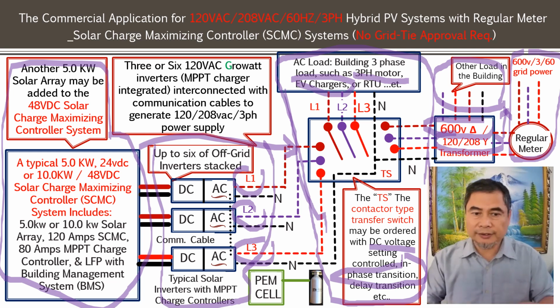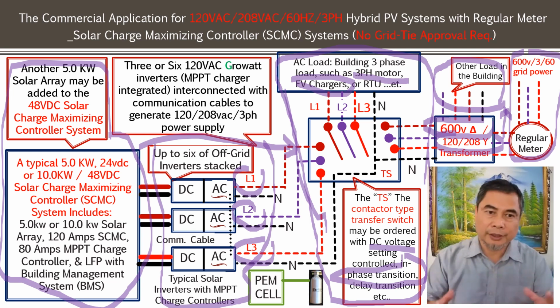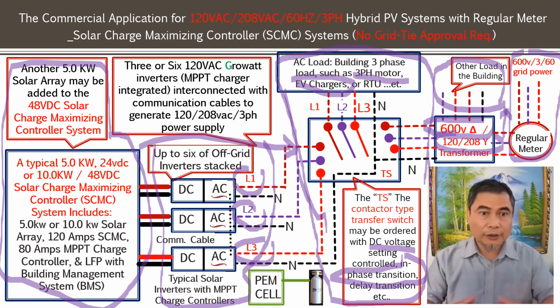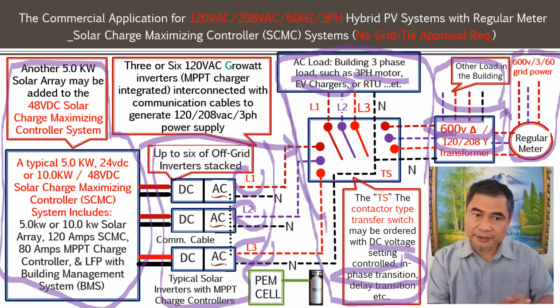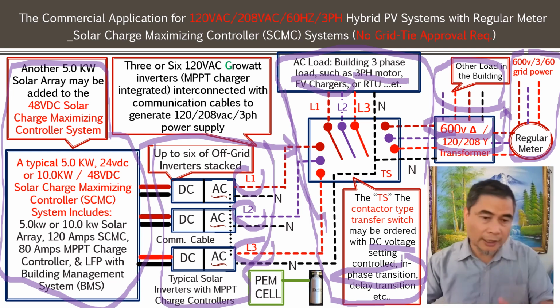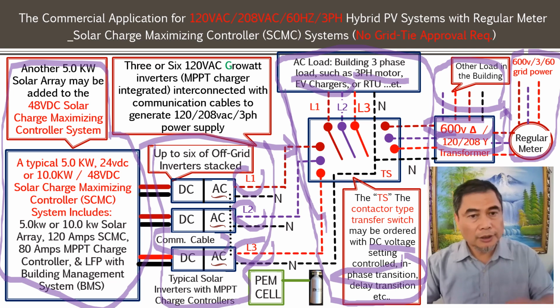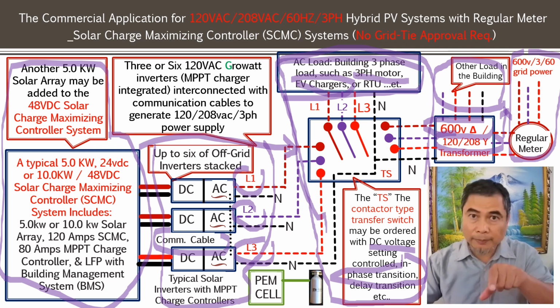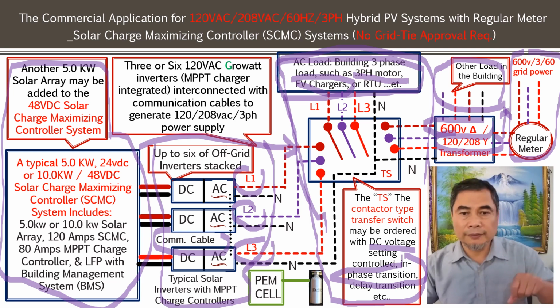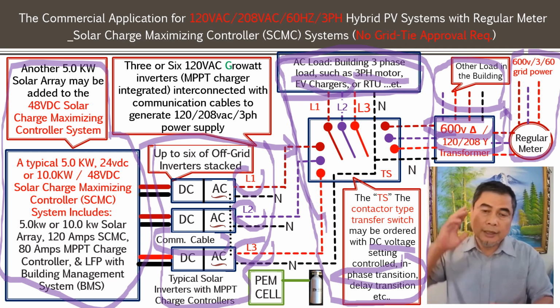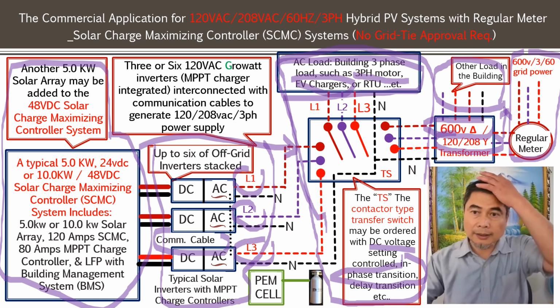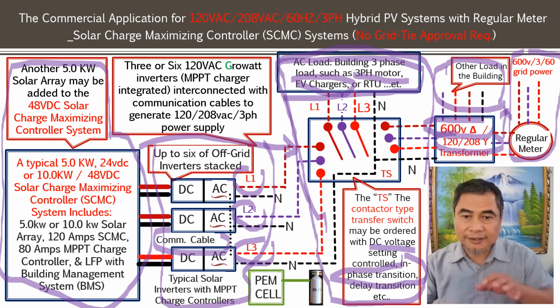We used this system for a temple building. They have enough room on the roof for a 20 kilowatt PV system, and then we have 6 of these off-grid inverters, connected through communication cable, to supply power to the three-phase system, including the rooftop unit and some kind of emergency power supply for the whole building, such as emergency lighting, in case you have a grid power outage and the system is still functioning.